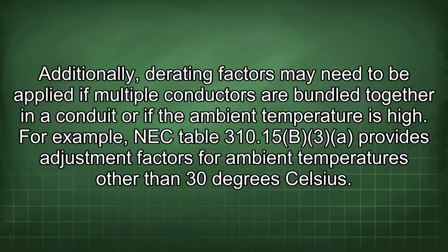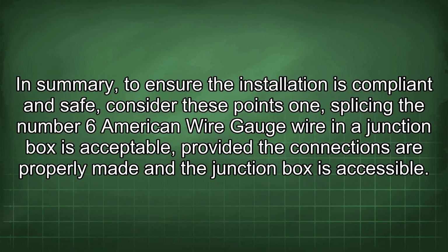Additionally, derating factors may need to be applied if multiple conductors are bundled together in a conduit or if the ambient temperature is high. For example, NEC Table 310.15(B)(3) provides adjustment factors for ambient temperatures other than 30 degrees Celsius. In summary, to ensure the installation is compliant and safe, consider these points.